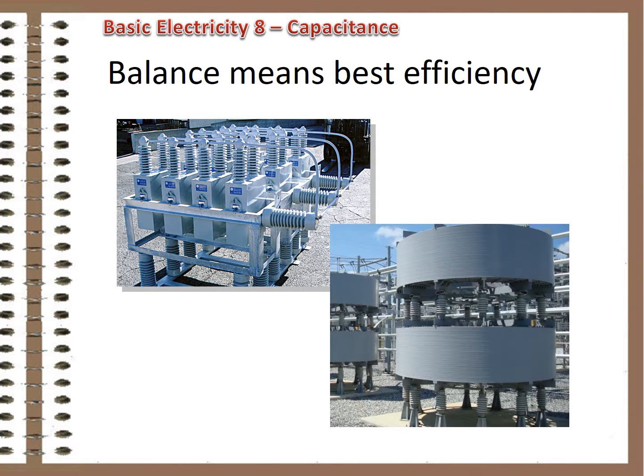Equal amounts of inductance and capacitance cancel each other out. Equipment — capacitor banks and reactor banks — are placed in the system to help with the balance. When inductance and capacitance are equal, or nearly so, most of the line capacity can go to transmitting watts, the real power that does work in the system.